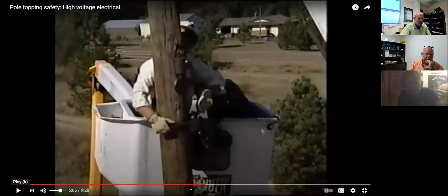Somehow we got out of the rubber glove discussion, and I guess that's because we went into line grounding. We used to use, back in the day, what they called a wire sling or wire rope sling. We discontinued use of those. Why? Well, one, it's a conductor, and if you get that thing anywhere close to an electrical line, that's not good. What else? They're notorious for fraying, and they'll fray at the connection points where they've been crimped. They'll poke through your leather glove, and sometimes through your rubber glove, and you'll never know it because it never reaches your finger. So don't use steel slings.